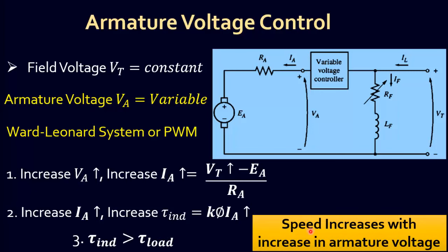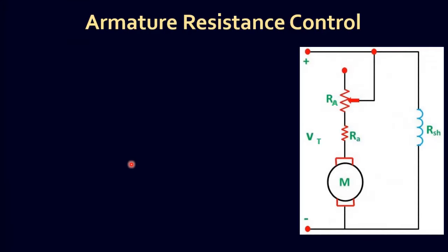In summary, as armature voltage is increased, the motor speed is increased. The last method is armature resistance control, which is the least common and most inefficient method of speed control. As you can see in the diagram, a variable resistor RA is added in series with the armature to control armature current IA.